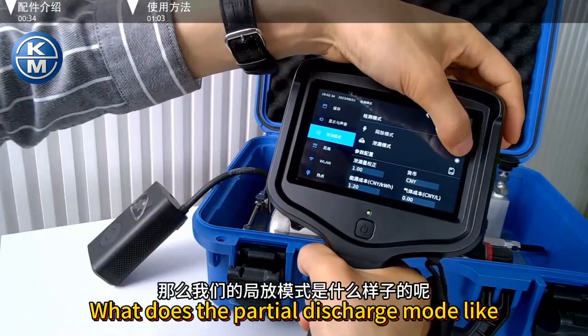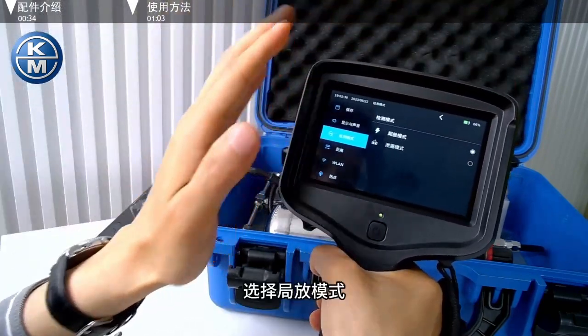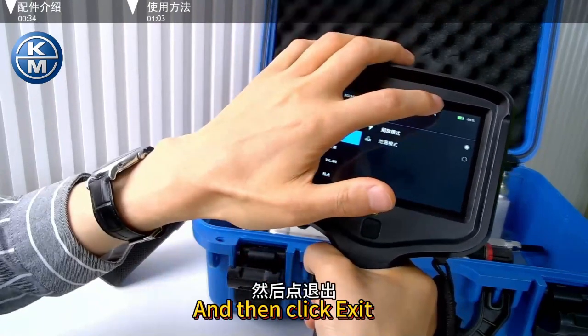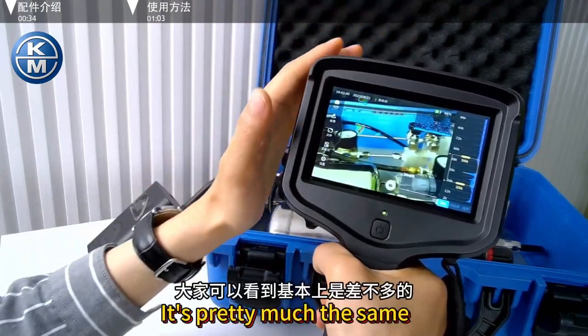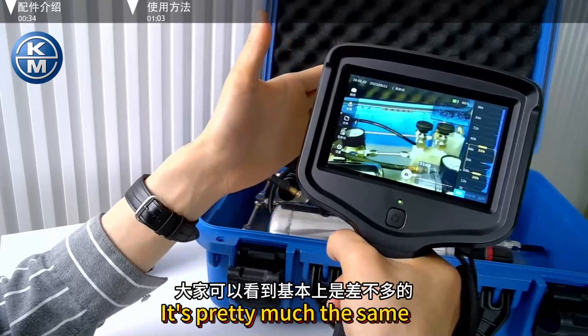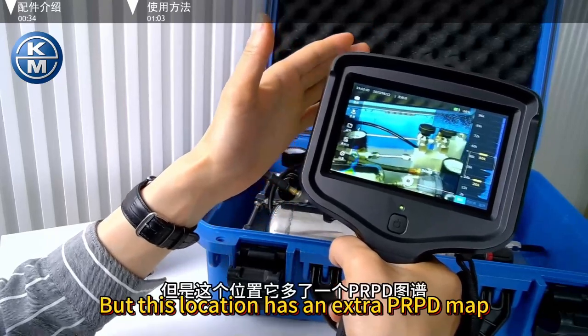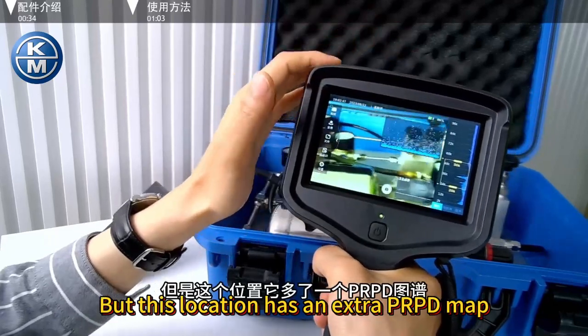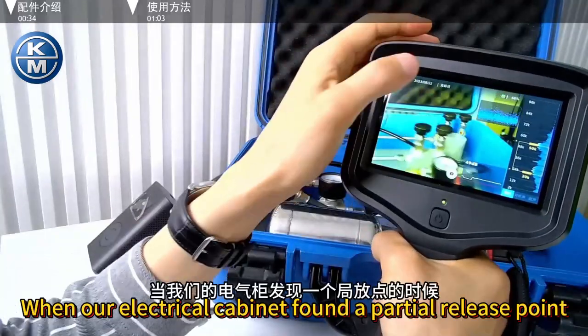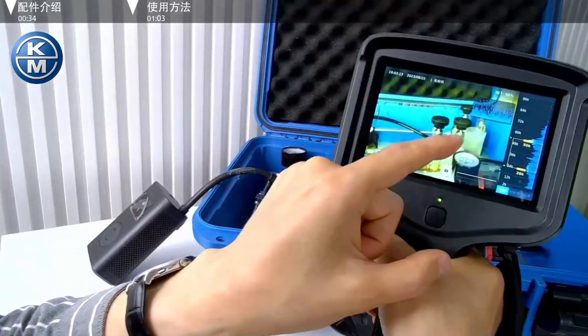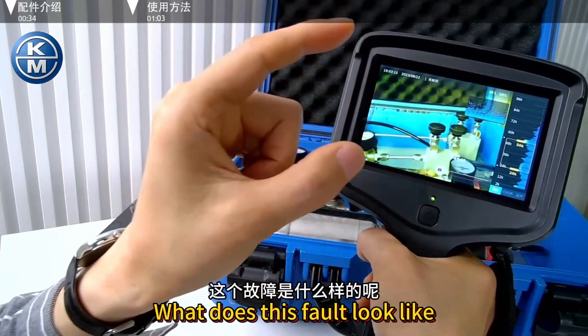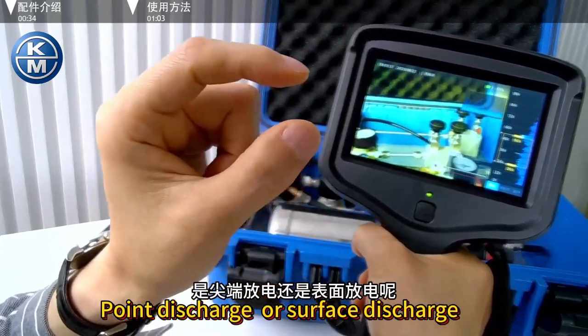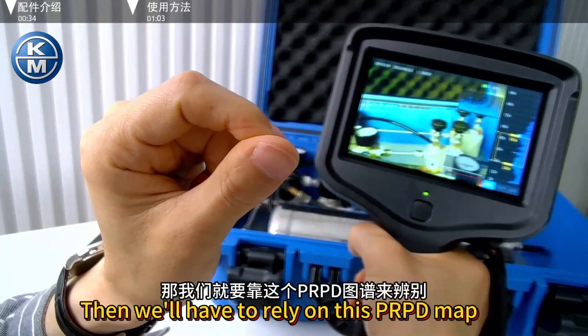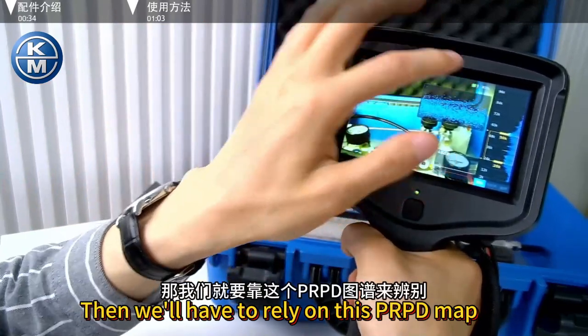What does the partial discharge mode look like? Select partial discharge mode, and then click exit. It's pretty much the same, but this location has an extra PRPD map. When our electrical cabinet has a partial discharge point, what does this fault look like? Point discharge or surface discharge? Then we'll have to rely on this PRPD map.